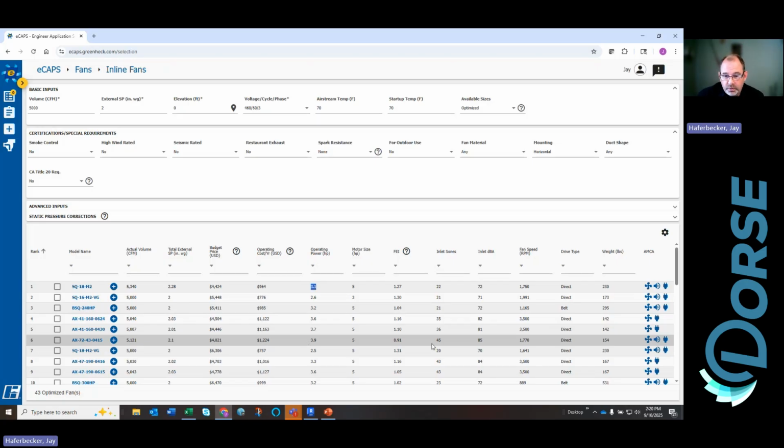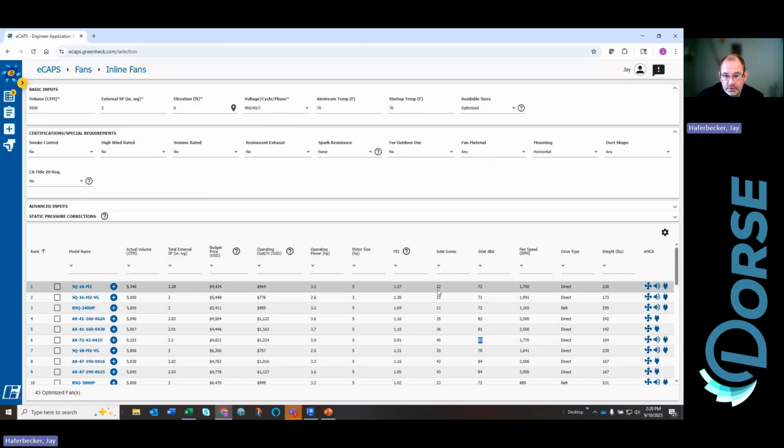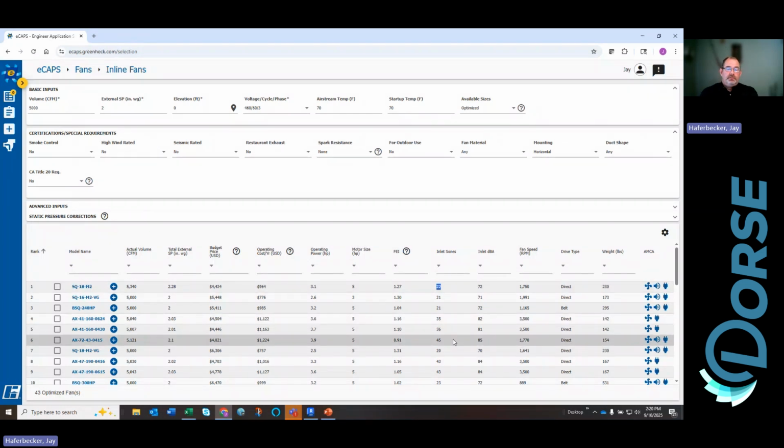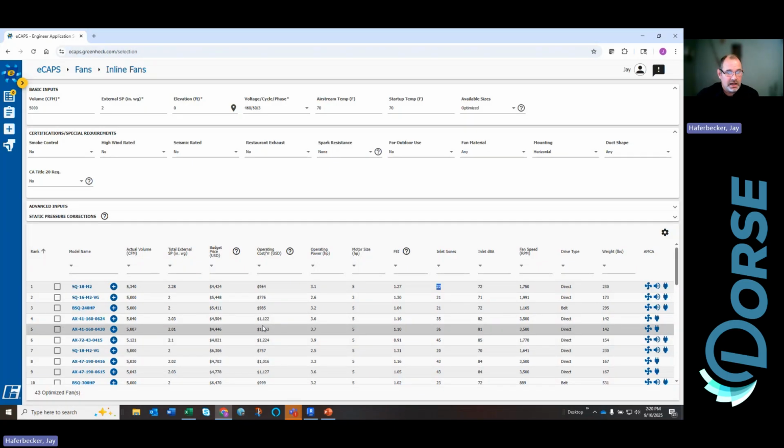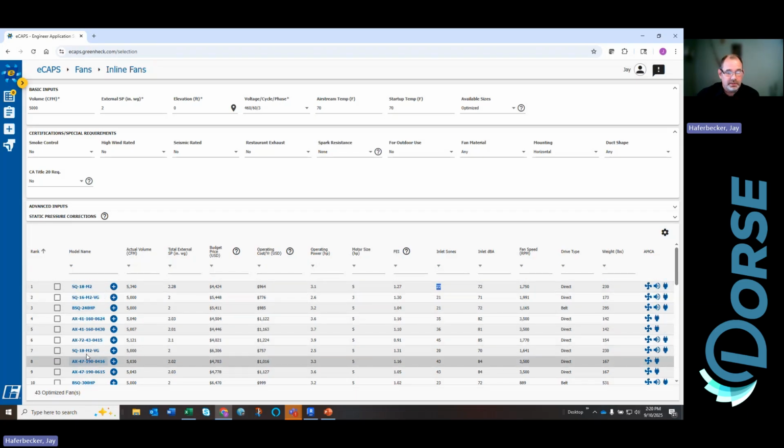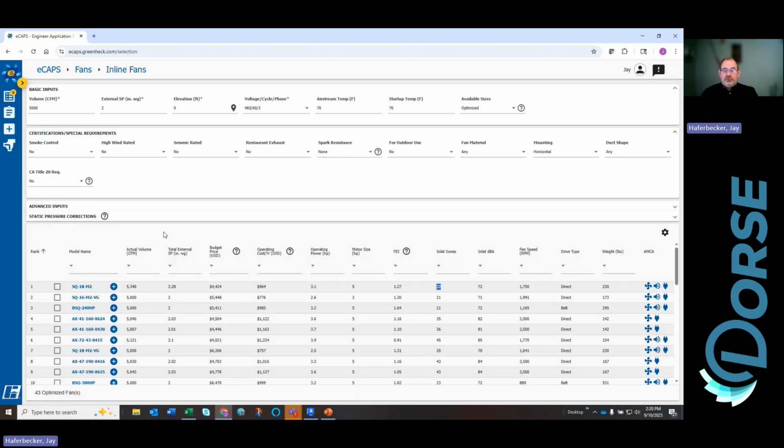What about the sound? Well, we went from 45 sones, or 85 dBA, down to 22 sones. That's almost half the sound. That's enough to matter, right? So that's what we're talking about with the ranking. We would recommend any of these top half dozen ranked items over any of the bottom ranked items all day long, right? But that's not my choice to make. That's your choice to make. We're just trying to guide you towards some of these better selections.